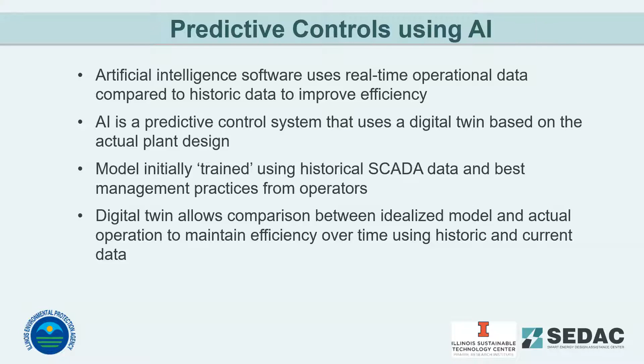The SCADA data forms a descriptive analytic model, showing how that plant has worked in the past. You can then analyze that data for a diagnostic analytic. A lot of times when we go into plants for our assessments, we're digging into this data for you, looking at historical data to figure out how your plant has reacted in the past. Sometimes we can do diagnostics by looking at whether your DO is swinging off set point significantly, and whether there's a way to optimize that. The nice thing about predictive controls and AI is that it builds this into your plant process and SCADA system automatically, continuously improving the plant and maintaining long-term energy efficiency.